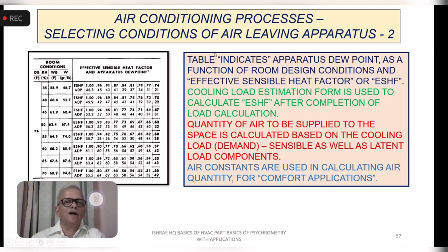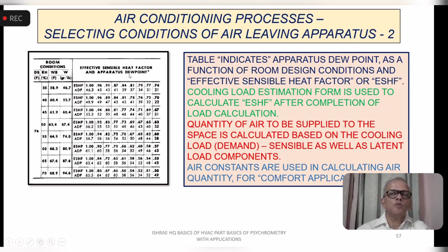We have seen this. The table is indicating the apparatus dew point as a function of the room design conditions and effective sensible heat factors. Cooling load estimation form is used to calculate the ESHF after the completion of this. Quantity of air is calculated and the air constants are used. So these tables are available for different room design temperatures. I have taken this as a sample, but if you see the ISHRAE data book, you will find different room design conditions available and with the range of relative humidity. So you pick up the correct table from the data book and then use these factors and compare and compute the capacities based on the requirements.